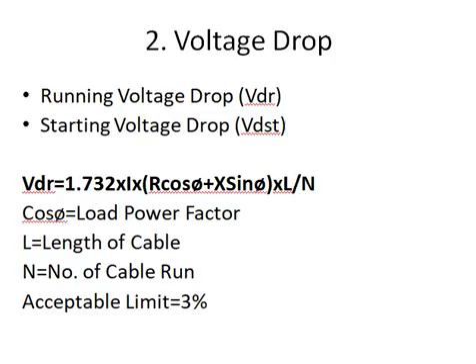Number two is the voltage drop criteria. There are two types of voltage drop: number one is running voltage drop, and number two is starting voltage drop. Running voltage drop applies to the normal motor running condition. The acceptable limit is three percent — that means during running motor condition, the motor bus voltage drop shall be limited within three percent.